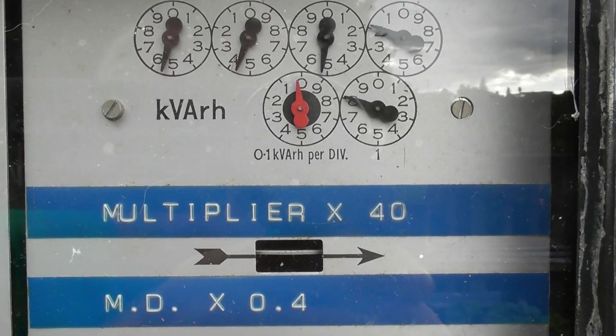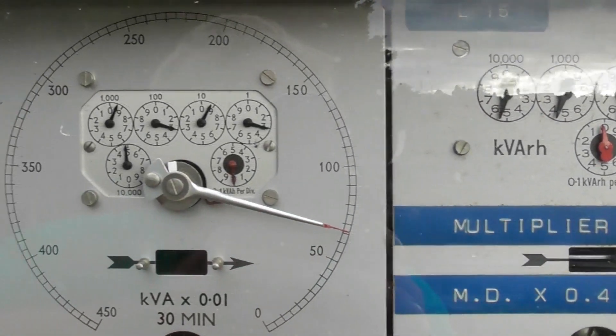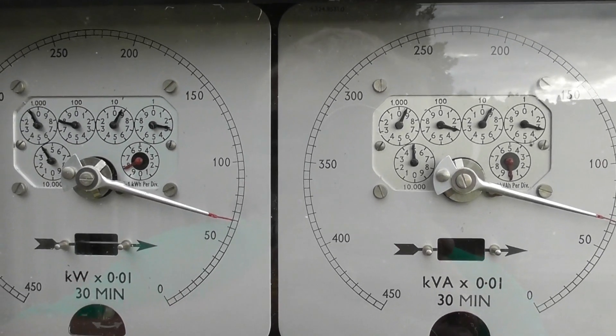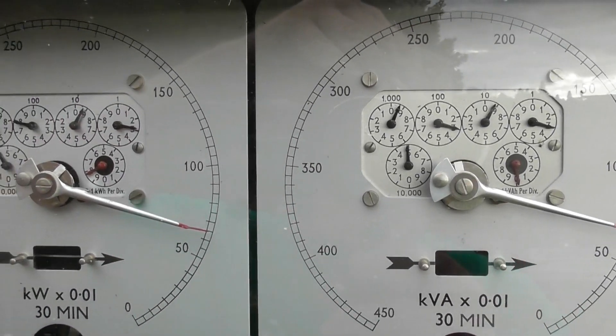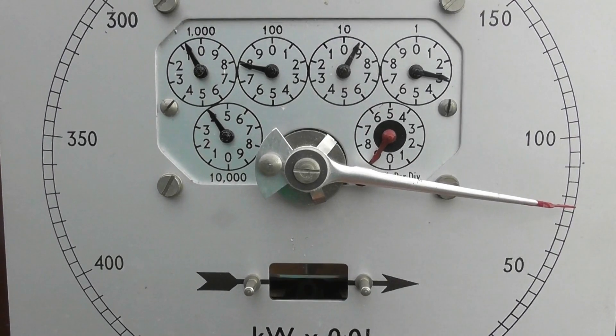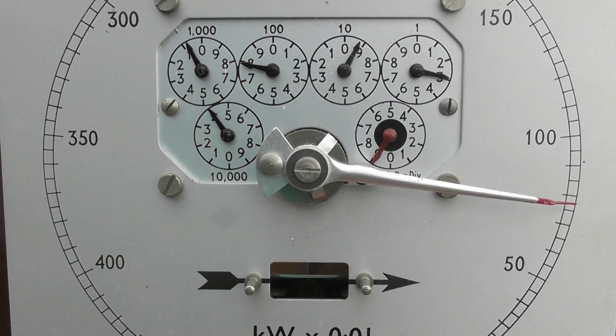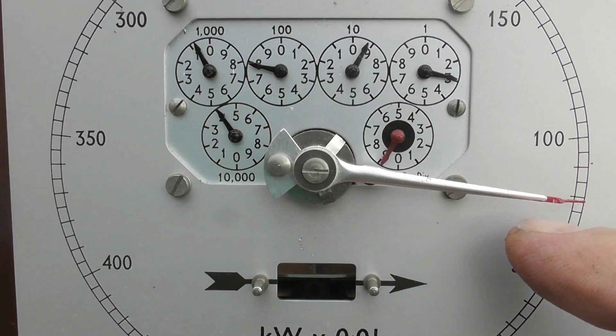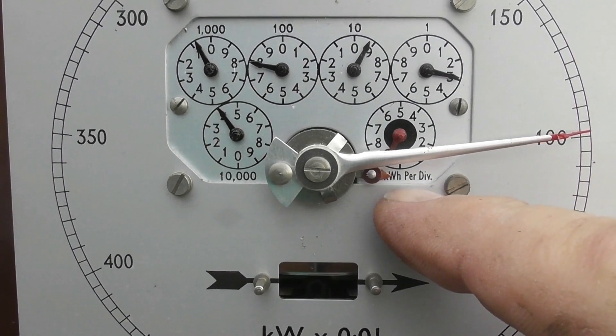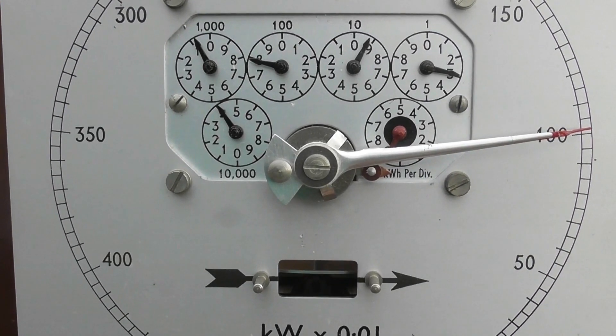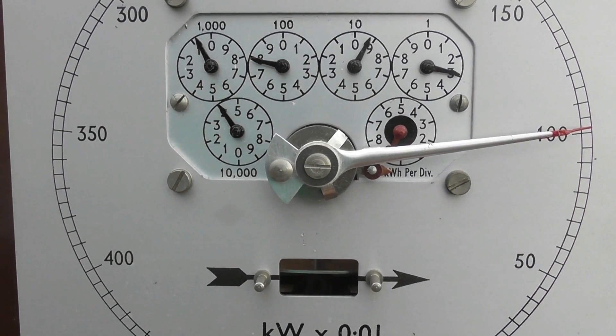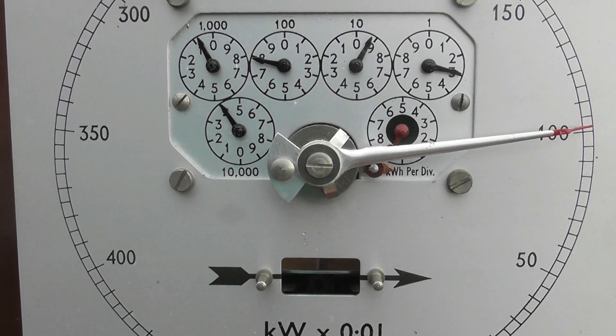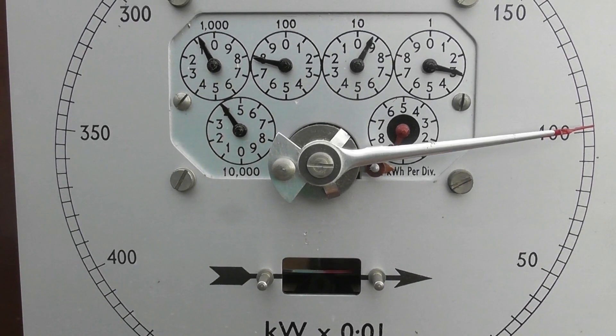I'll try to put a fully inductive load on the meter and explain exactly how it works. On this particular meter, I'll take the cover off and we get a bit better view with less glare. The demand indicator is rising at the moment. You'll see there's a little pusher, a little red pointer which resets every 30 minutes. So when there is a load on it increases until the 30 minute event happens and it drops the little pointer back.